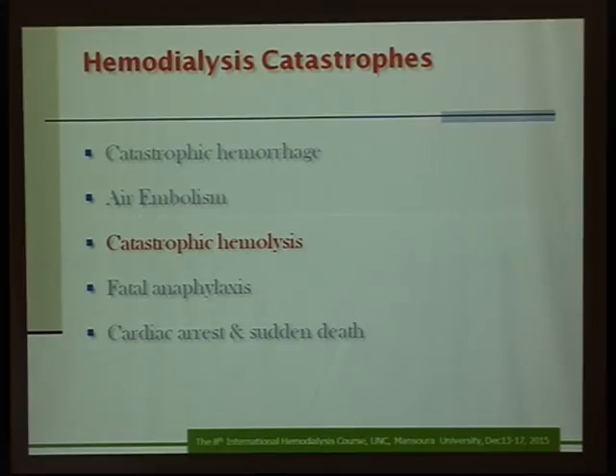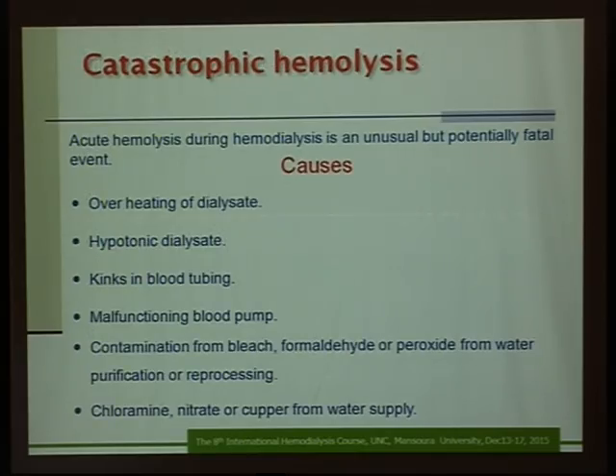The third catastrophe is the development of hemolysis. Again, it's unusual, but it is potentially fatal. Hemolysis is the result of destruction of the RBCs by overheating of dialysate, using hypotonic dialysate, kinks in the blood tubes, malfunctioning of the pumps, maybe contamination of the dialyzers by formaldehyde or chloramine, nitrate or copper from the water supply. All these will cause oxidation and reduction of the RBCs, leading to their destruction and hemolysis.